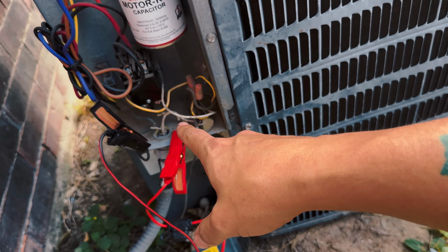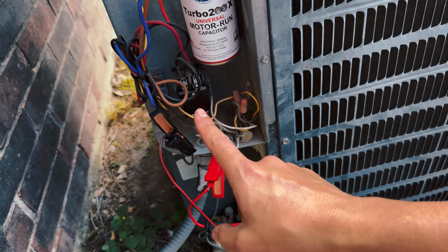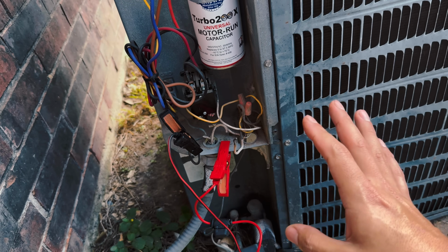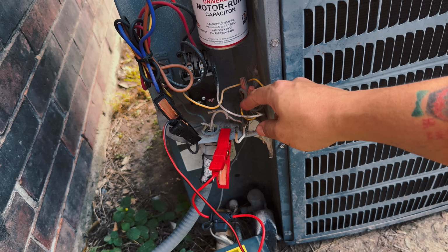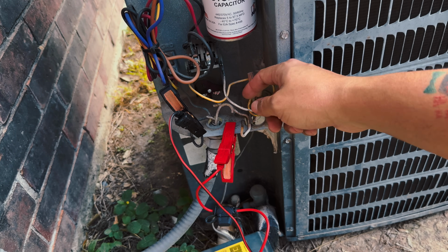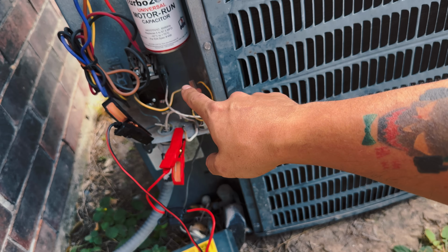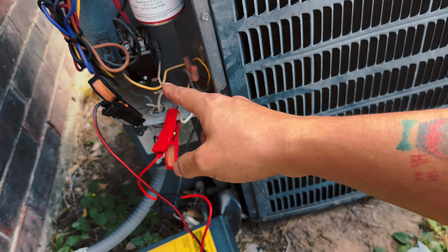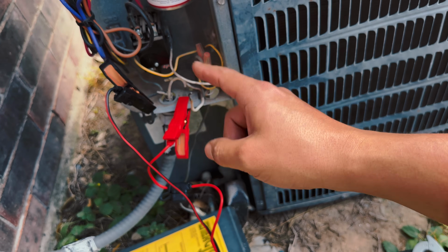So we are disconnecting the wires from the contactor, making sure the thermostat is off, so we don't get any voltage on these and short anything out - you know, low voltage, 24 volts. Make sure nothing happens there. And then our high voltage is completely disconnected from the line side.